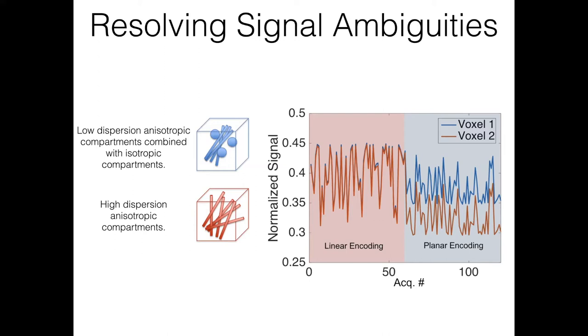We're sensitive to many different features of tissue microstructure, but it's hard to tease apart changes because different tissue alterations can produce the same measured effect. For example, two different voxels can appear similar with linear encoding — one with low-dispersion anisotropic compartments combined with isotropic compartments, another with highly dispersed anisotropic compartments. With planar encoding, we can start to disambiguate between them.